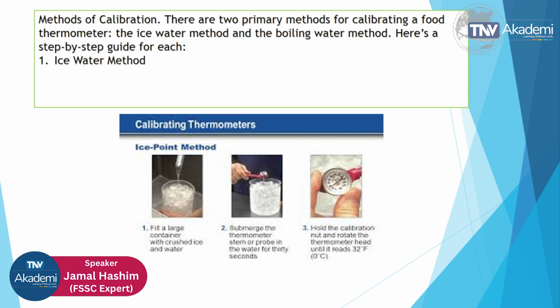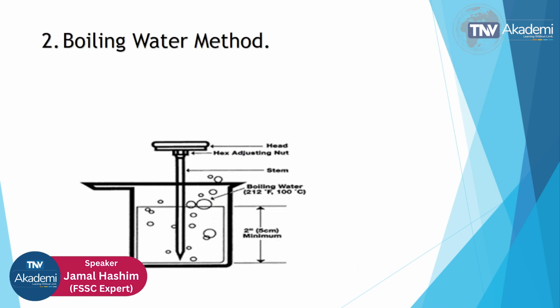Now the second one is the boiling water method. In the boiling water method, what are the materials we need? A pot of clean water, a heat source, a food thermometer, and a wrench or plier. In the procedure, first boil the water. Bring a pot of clean water to a rolling boil. Insert the thermometer. Insert the probe into the boiling water, not touching the sides or bottom. Now wait for stabilization. Wait for the reading to stabilize, about 30 seconds to 1 minute. Check the reading. The thermometer should read 212 degrees Fahrenheit or 100 degrees centigrade at sea level.